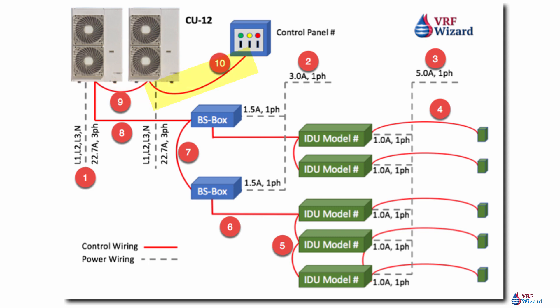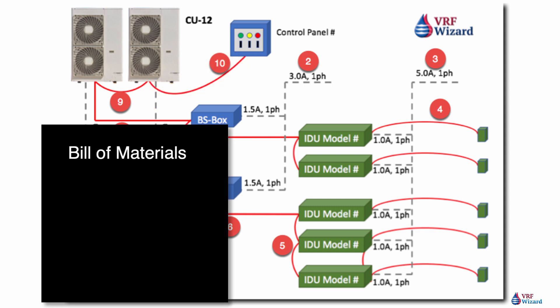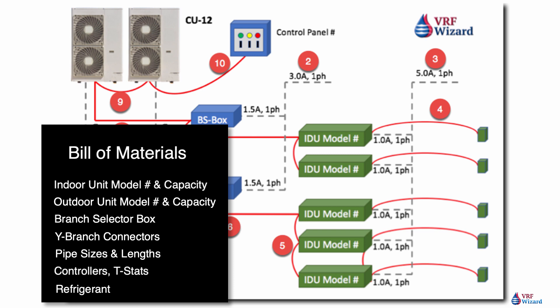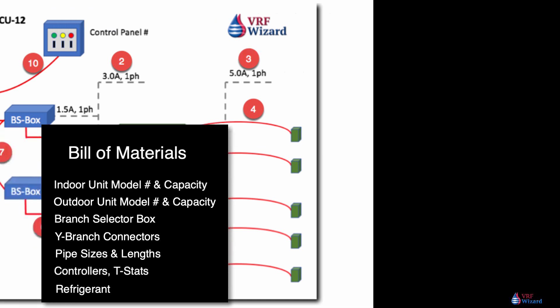The bill of materials: the VRF piping design software will provide a bill of materials for the project, which should include at minimum the equipment model numbers and capacity, accessories like branch selector boxes, Y branches, headers, pipe sizes and lengths, the controls required, thermostats, the factory refrigerant charge, and the additional refrigerant charge required for all the lengths of your pipe. The VRF software can also generate an equipment schedule to be used on your CAD design drawings.